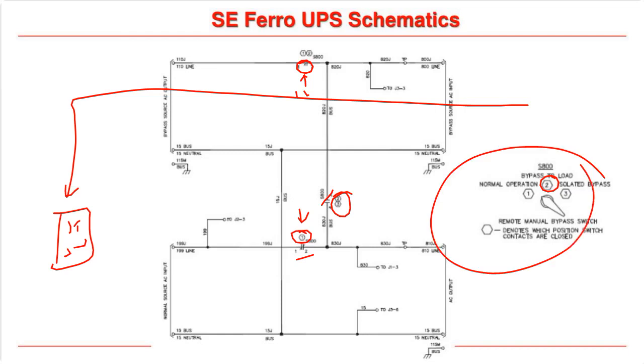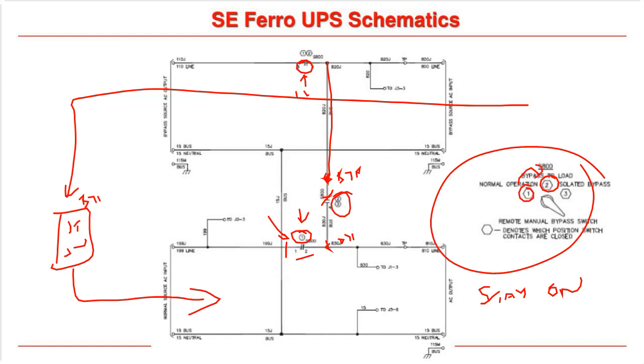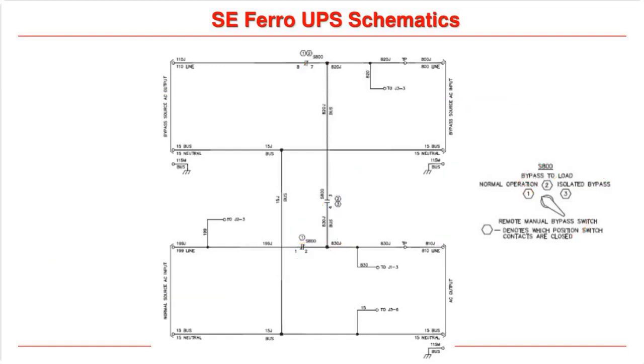Before you roll this switch from position 1 to position 2, or position 2 to position 1, you should always put the static switch to bypass, okay? So our bypass is going to be coming out through here now. And that ensures that this side, which is connected to the bypass directly here, is bypass, and this side here is bypass. So when we roll this switch to position 2, we are paralleling bypass and bypass together before this one here opens. That's what allows us to have the make before break arrangement. So your load circuits will stay on. They'll continue to be powered when you roll that switch from position 1 over to position 2. So that's kind of complicated.